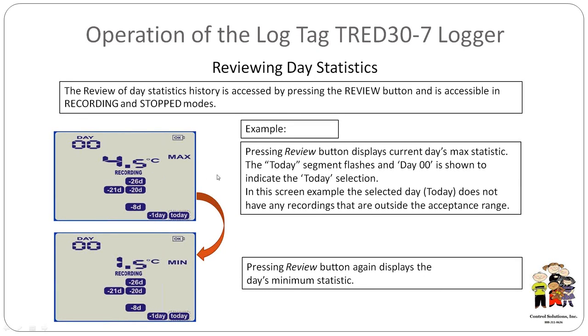So what I'm looking at here is that I have pushed the top button on our logger, as we looked at in our previous display. What that top button is going to do is be used as a review and mark chart. So if I came into my clinic and I pushed the top button, it's going to display the maximum temperature since midnight. So it would be my suggestion that every morning, 8:35, whatever time it is that you do your first inspection, that you review this data. It's going to give you a kind of health indication of how well your refrigeration unit operates without the daily need to open and close the door.